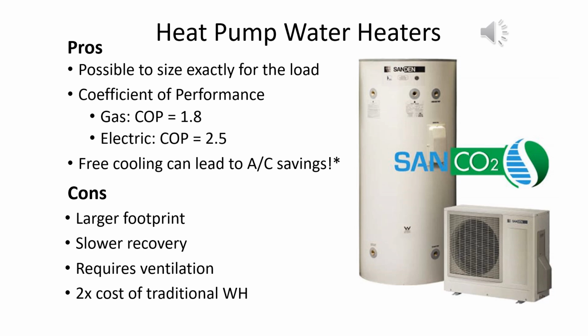Heat pump water heaters can be packaged or split, which refers to whether the evaporator is connected to the hot water tank or remote. If the evaporator is placed in a hot room in the facility, the heat pump can provide some free cooling as an added benefit. The cons are that these units require large volumes of hot water storage to compensate for their slower recovery, which means that they require a larger footprint. Heat pump water heaters also require ventilation and have about twice the upfront cost of traditional water heaters, so there are significant barriers to their widespread adoption in the commercial food service industry without some level of incentivization.